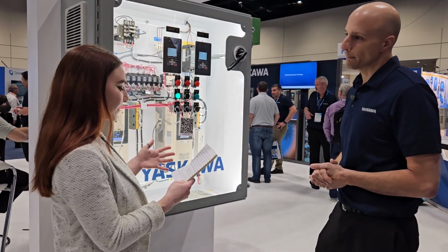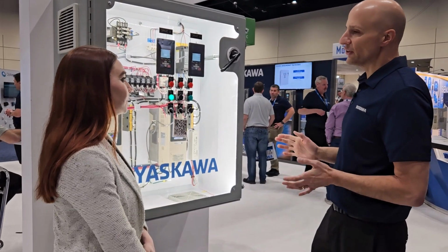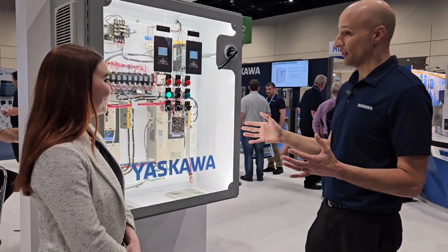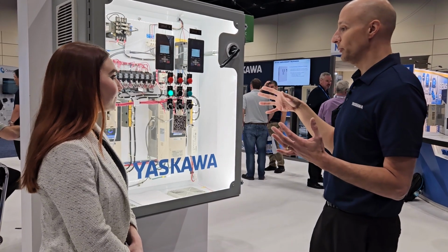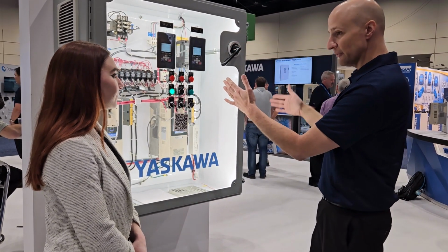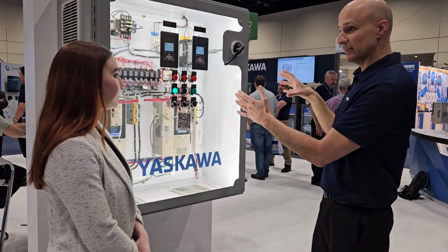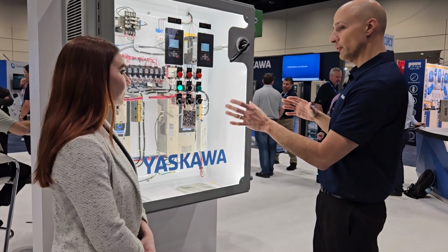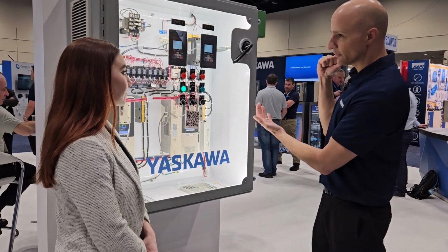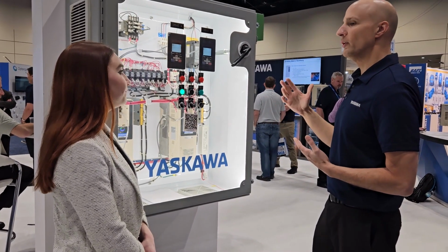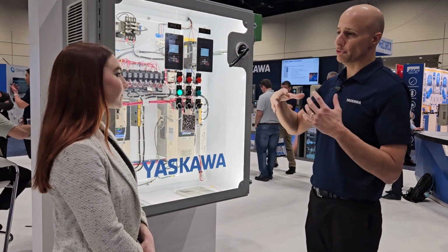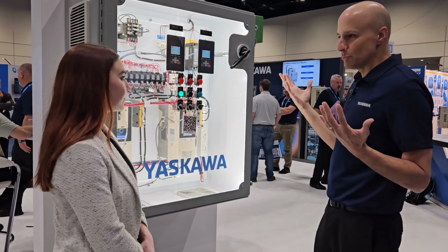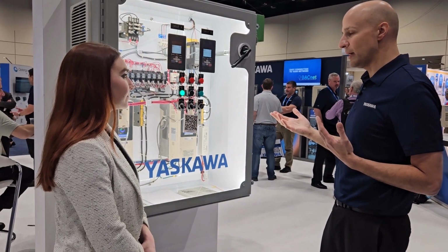And so is this specifically better than a bypass with drive? It has its advantages. A drive with bypass is exactly what it sounds like if you think about it from the electrical perspective. The bypass actually bypasses the drive by running the motor across the contactor. So the drive gives you the variable speed, but if you switch over to bypass, let's say the drive were to fail, now we run in bypass, that contactor closes, we have no speed control. We have a high inrush of current, it could be obnoxious: pressurized ductwork, noise, belts squealing, lights dimming. There's a lot of drawbacks potentially to a bypass.